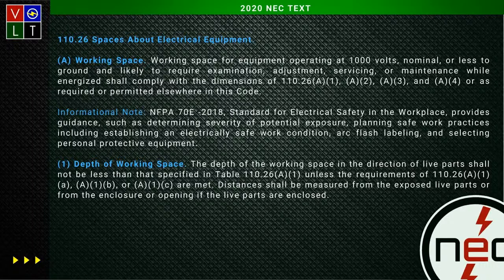We actually made changes. A while back, some of us were the only ones teaching the 70E classes for NFPA, because some other instructors didn't fully understand 70E at the time since it was new. They were saying just pick a similar task and apply it to that hazard risk category. That got back to the 70E committee, and we said no, that's not right. I was actually helping on the task groups that put those tables together, and now we specifically let you know that if that specific piece of equipment and task isn't listed, tables 130.7 C15A, B, and C do not apply.